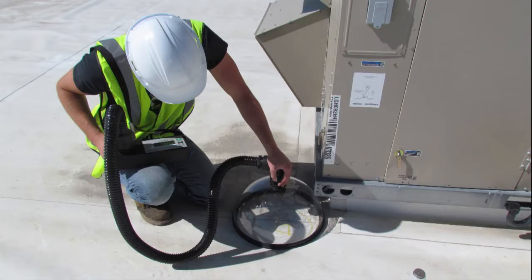As a point of background, the ANSI/ASHRAE IES Energy Standard 90.1 2010 and the International Energy Conservation Code 2012 require that building envelopes be designed to control air leakage. The IECC also designates paints on concrete block as an air barrier. In order to comply with the mandate to restrict air leakage, a variety of materials are used during construction. Testing is also performed to confirm that leakage doesn't occur.